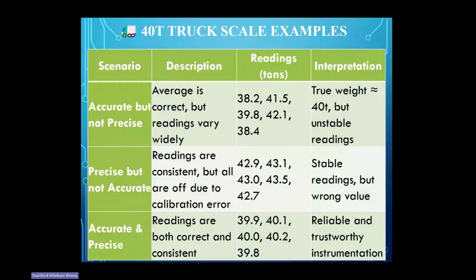Then in the third scenario, we have 5 loads: 39.9, 40.1, 40.0, 40.2, and 39.8. When we check this and average it, it gives us about 40 on average. Also, when we round off to the nearest 10, we get 40, 40, 40, 40. And when we do our average, it gives us the 40 that we need. So then we go thumbs up. This is what we do. Then what we do is go and check the calibration file that we have used.